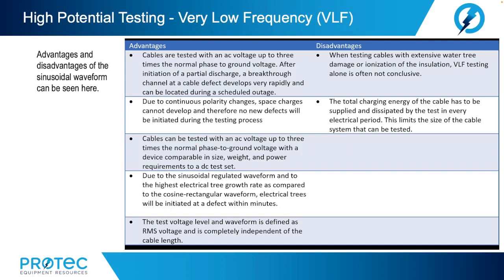Another advantage, due to the sinusoidal regulated waveform and to the highest electrical tree growth rate as compared to the cosine rectangular waveform, electrical trees will be initiated at a defect within minutes. And also among the advantages, the test voltage level and waveform is defined as RMS voltage and is completely independent of the cable length. The disadvantages of the sinusoidal VLF waveform.